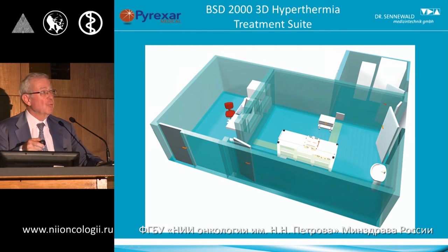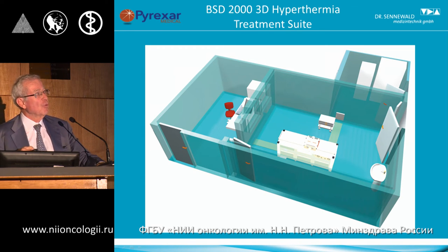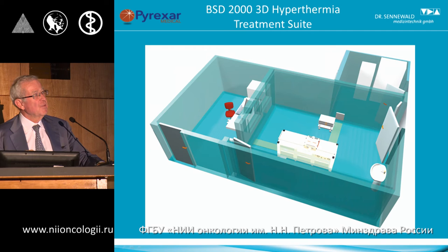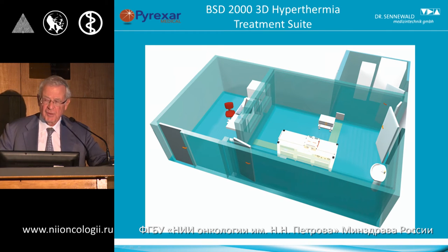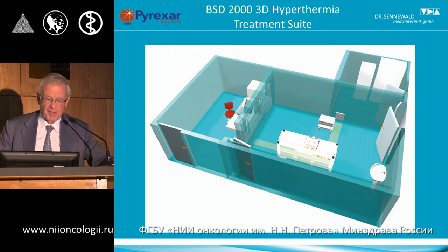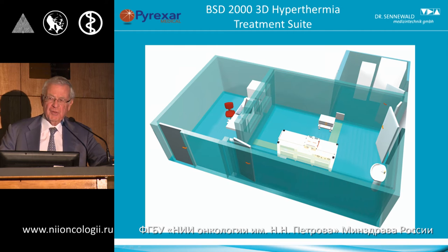This is a schematic view of the installation. You have three rooms: a control room, a technical room with a couple of square meters to locate the amplifiers, and a shielded room — a Faraday cage. The Faraday cage is essential because the operational frequency range around 100 megahertz is the exact frequency range of television and radio.